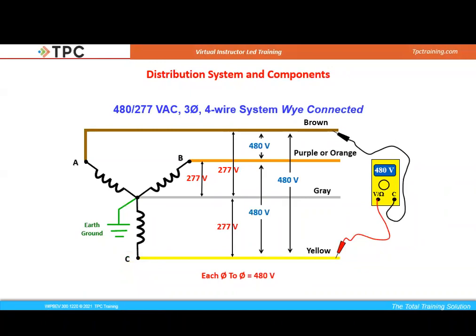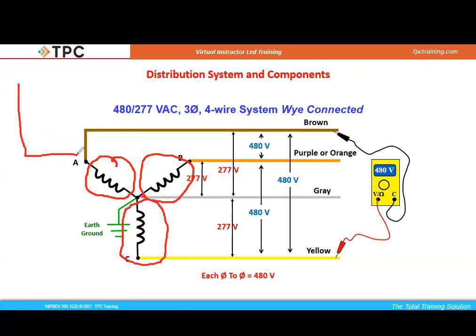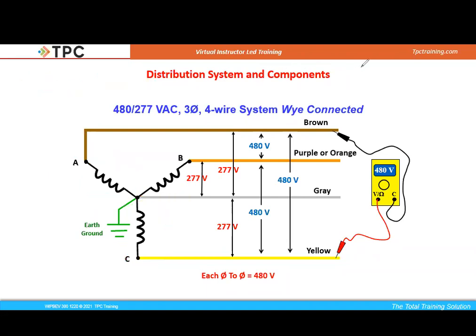In the poll that we conducted earlier that Ryan distributed to you, you said that 480-277 was everywhere in your facility, right? And so this is exactly what we would have. We would have three transformers outside your facility somewhere, either hanging on a pole or inside an enclosure. If they were inside of an enclosure, there would still be three transformers here, but you would only see one enclosure. So you would have to know what the system was, if it was three phase or single phase. Because when you look at it, you think, oh, there's only one enclosure there, it must be single phase. No, because sometimes we put three transformers inside that one enclosure. And in this particular case, we have connected the transformers in what we call a Y configuration because it looks like the letter Y, right?